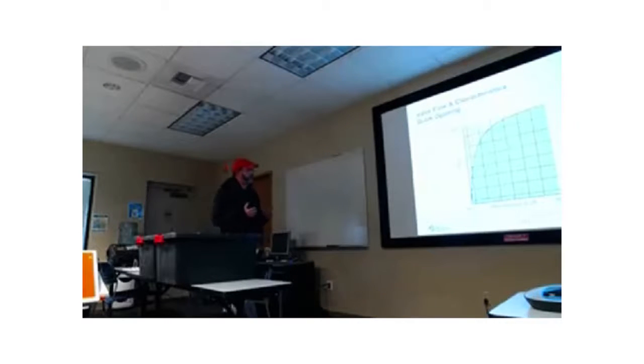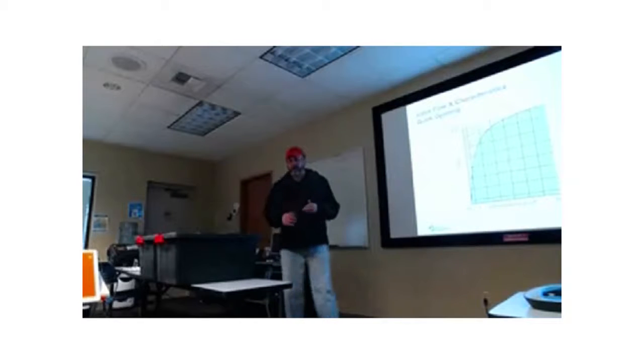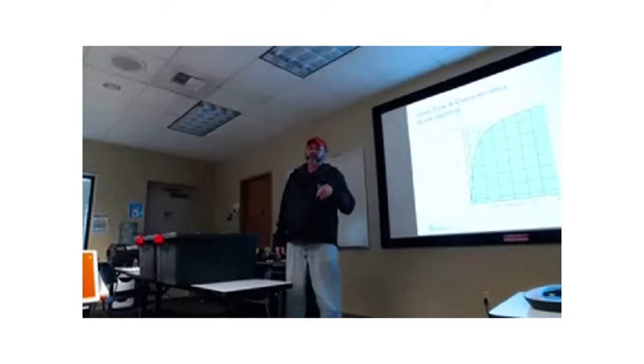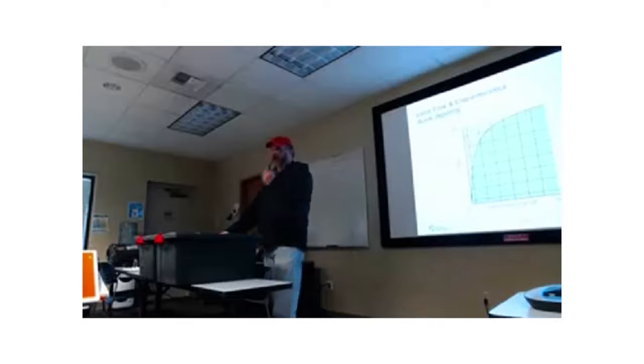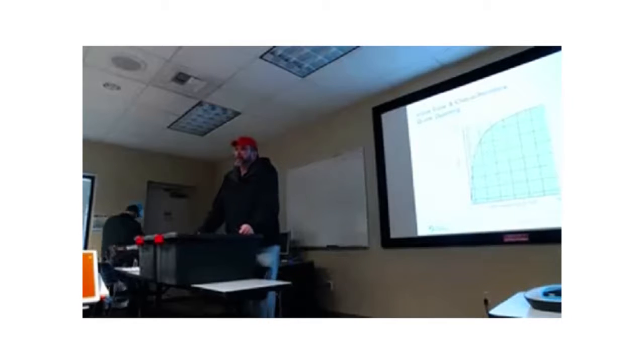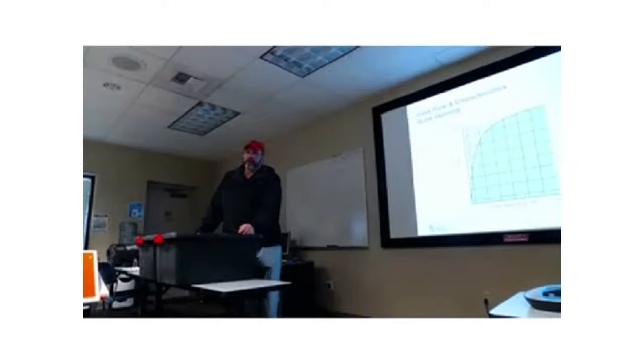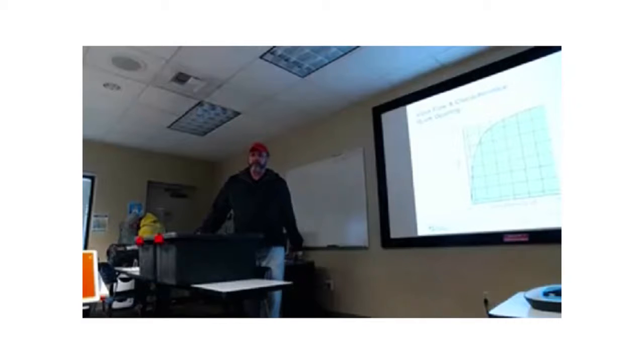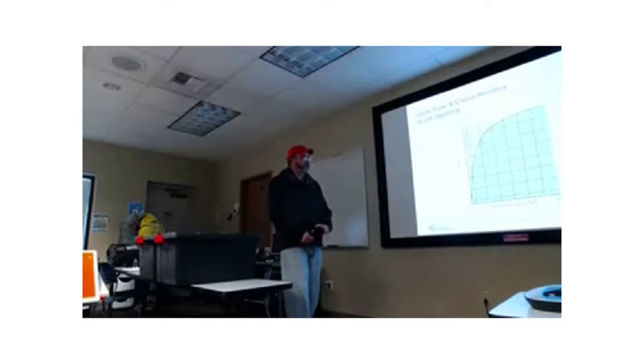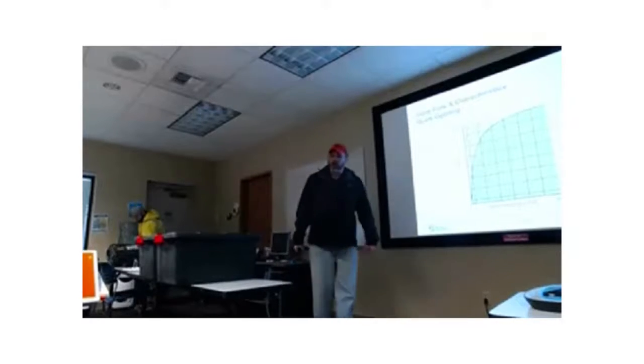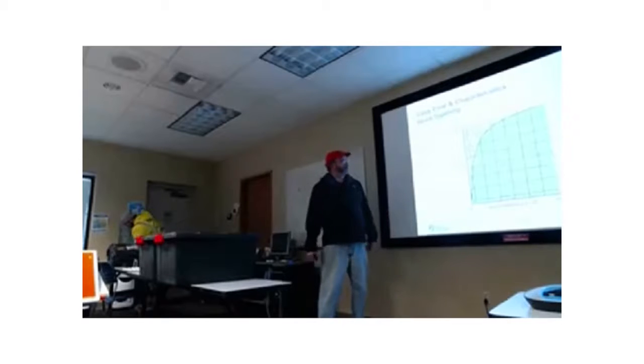This is what we're going to talk about now. I'm just going to talk about valve characteristics. So again, how does this relate to you? You can have situations where people put the wrong type of valve in, and if you get the wrong type of valve in, they may not get the kind of control that you want. So people complain, I can't maintain the temperature, I can't maintain my discharge air temperature, what the hell is going on? So this is where, sort of like level 2, you go into, well, okay, what kind of valve do I have in there?